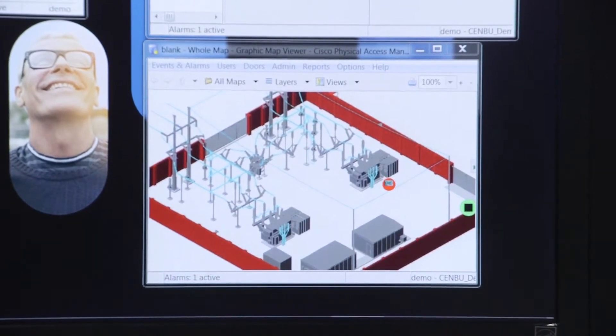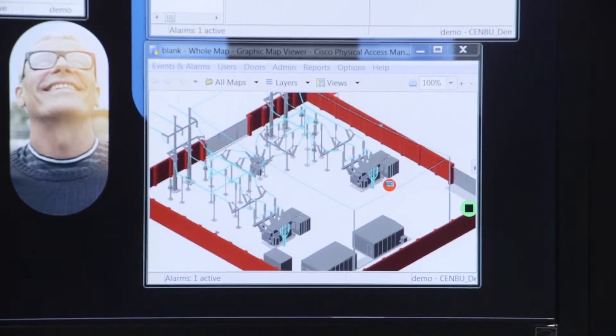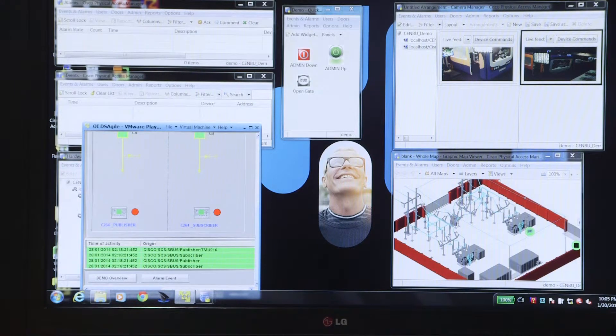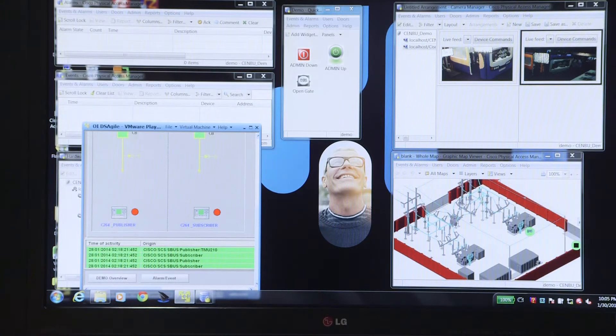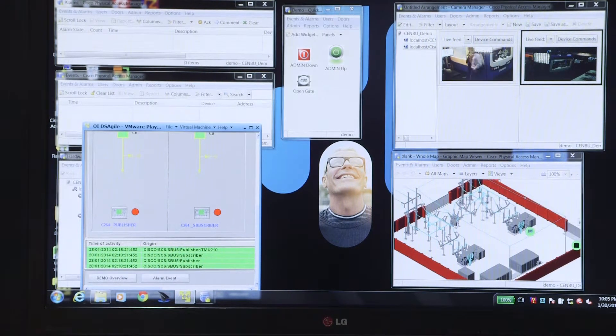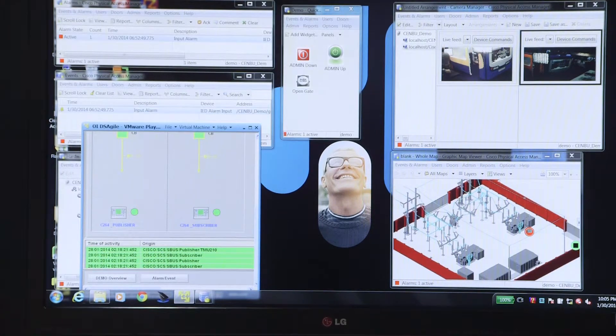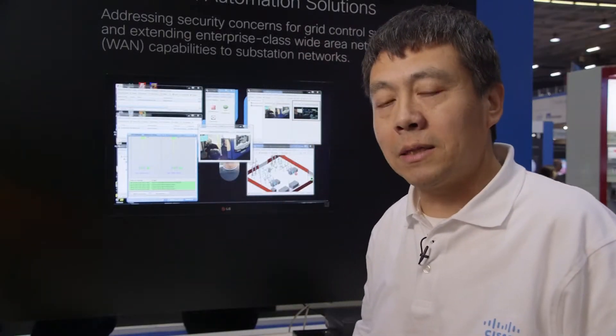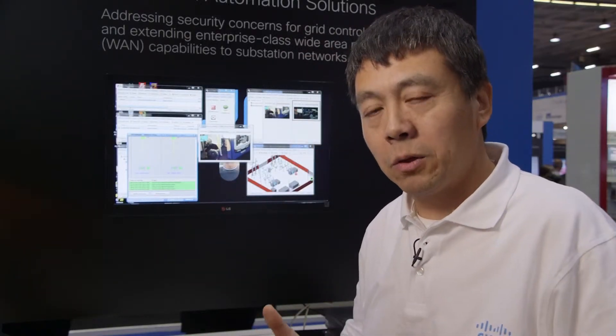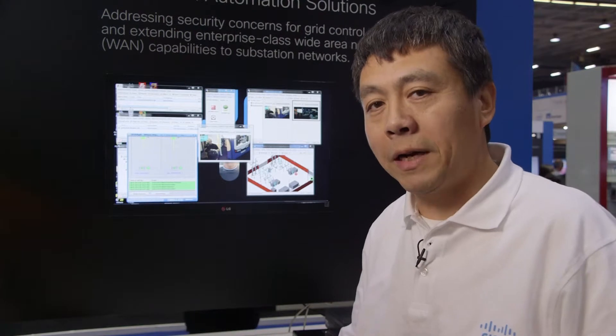First of all, we notice that the HMI status has been updated immediately, which means the protection device detects the fault and trips the breaker to protect the feeder. And the other protection device is also being tripped to protect another feeder, so the entire substation is fully protected.